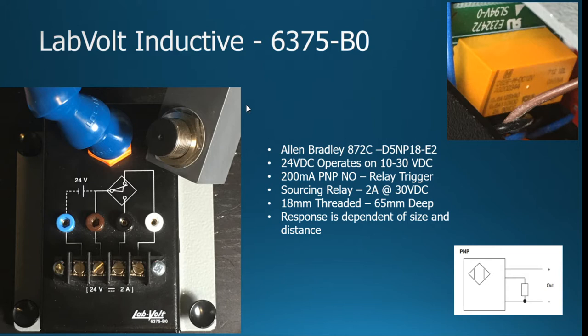As far as the response on this, it actually is dependent on the size and the distance. And what's kind of interesting is how the inductive sensor works. It's actually DC running here, but it actually has to go through and create an oscillating signal. So it's actually going to create some alternating current on a ferrous coil.